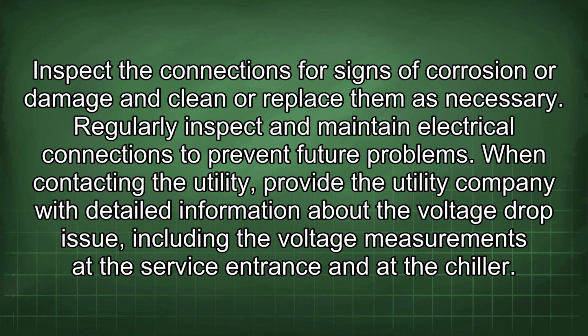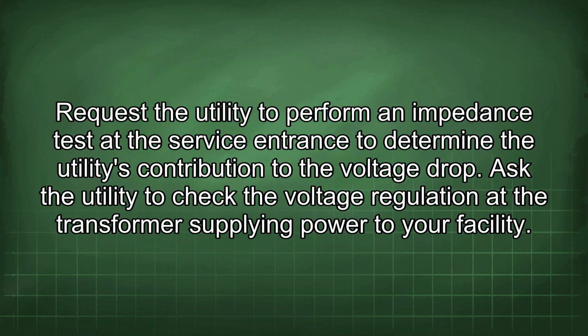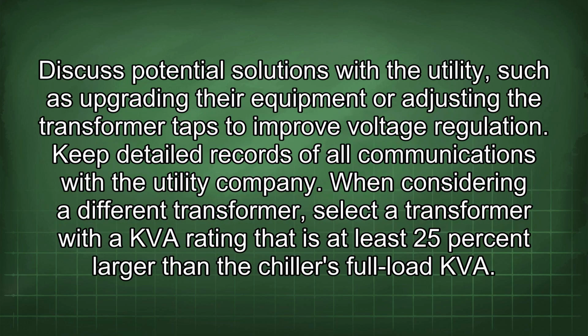When contacting the utility, provide the utility company with detailed information about the voltage drop issue, including the voltage measurements at the service entrance and at the chiller. Request the utility to perform an impedance test at the service entrance to determine the utility's contribution to the voltage drop. Ask the utility to check the voltage regulation at the transformer supplying power to your facility. Discuss potential solutions with the utility, such as upgrading their equipment or adjusting the transformer taps to improve voltage regulation. Keep detailed records of all communications with the utility company.